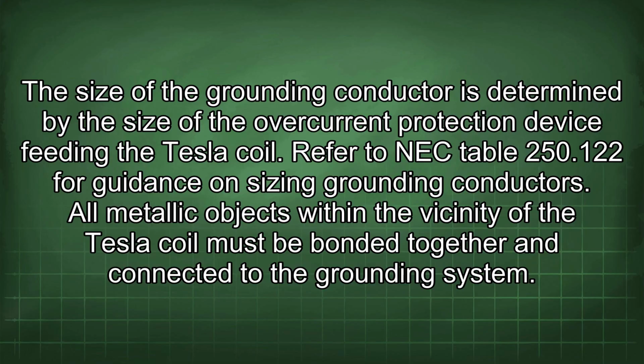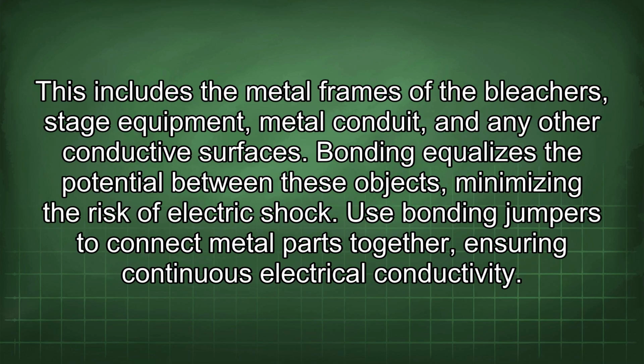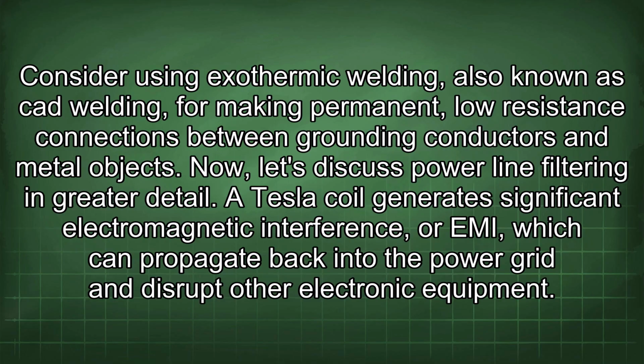All metallic objects within the vicinity of the Tesla coil must be bonded together and connected to the grounding system. This includes the metal frames of the bleachers, stage equipment, metal conduit, and any other conductive surfaces. Bonding equalizes the potential between these objects, minimizing the risk of electric shock. Use bonding jumpers to connect metal parts together, ensuring continuous electrical conductivity. Consider using exothermic welding, also known as CAD welding, for making permanent low-resistance connections between grounding conductors and metal objects.